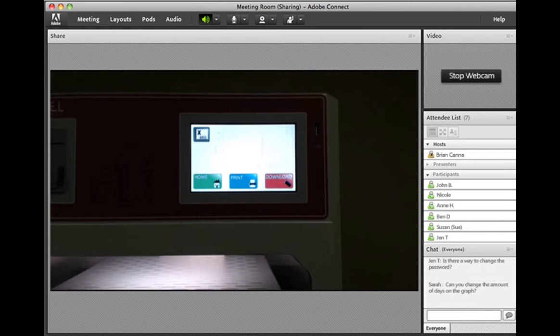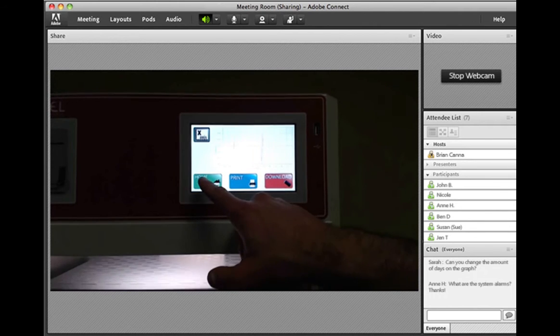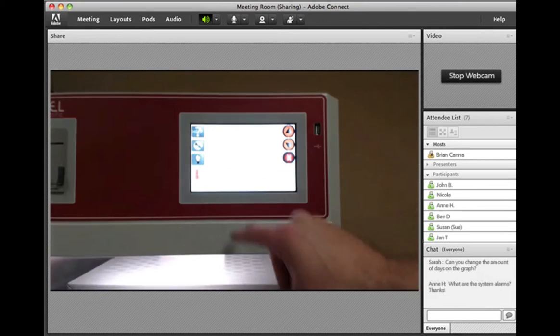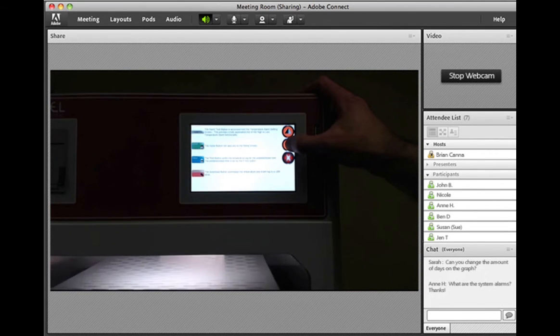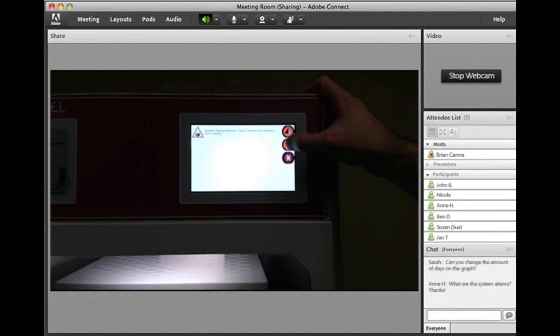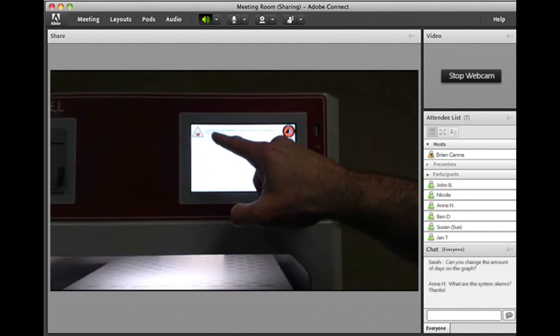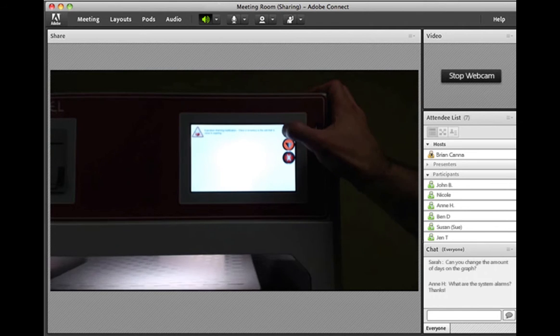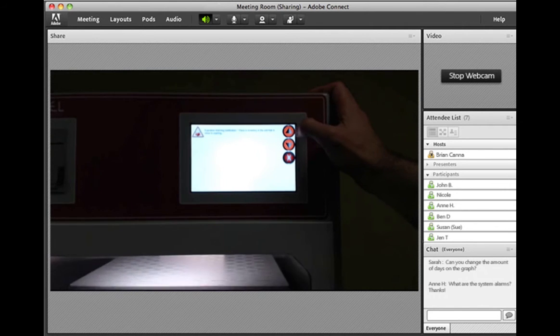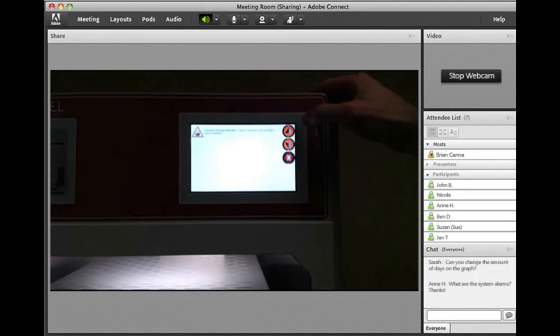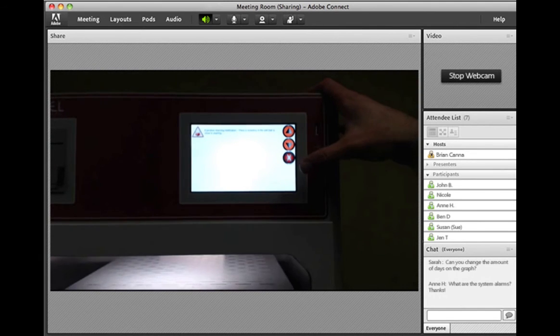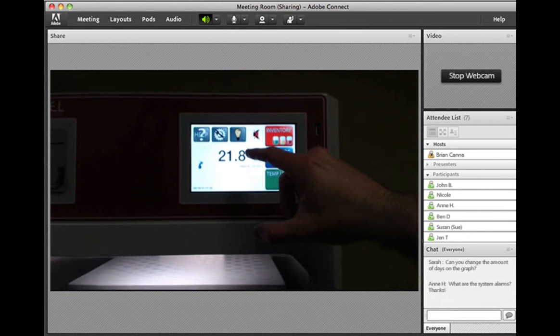So it looks like we have another question. It's from Ann. It's about the alarms on the system. And I think the best way to go through those alarms is to go back into the home menu and then go into the help and run down to the bottom of this to show all the different alarms of the system. So here we have one alarm. It's an expiration warning notification. So this is tied to the inventory management system, and this alarm has a bag that's approaching expiration. Now you can configure these alarms in the settings menu, and I can actually show you real quick how to do that.